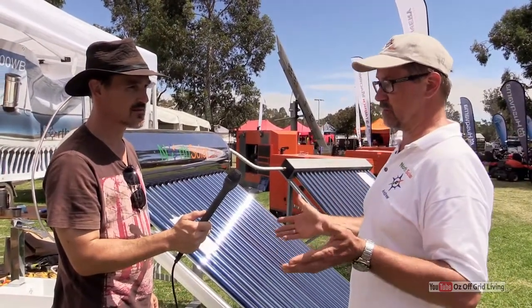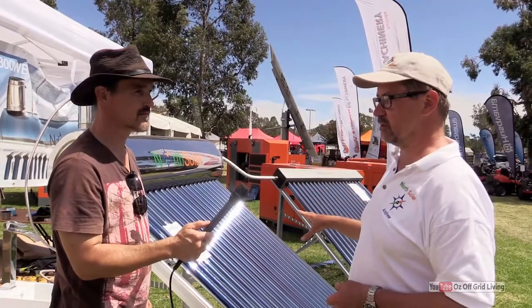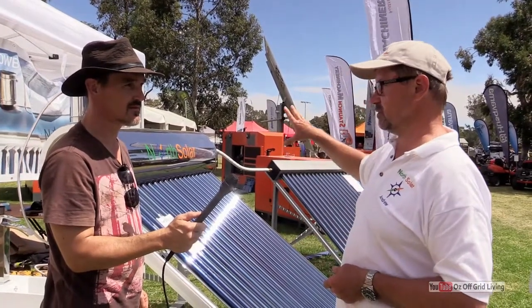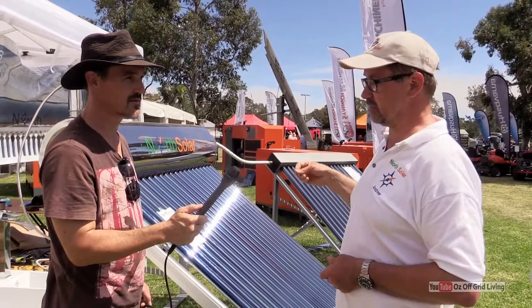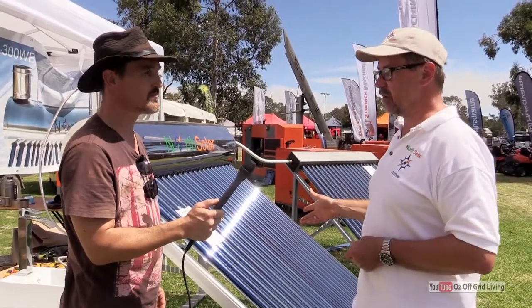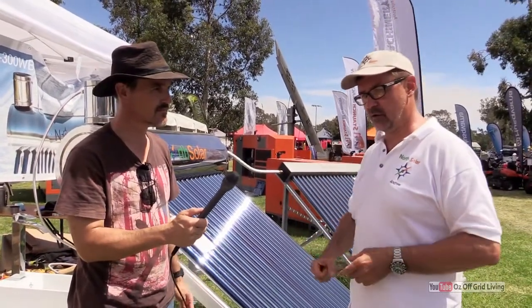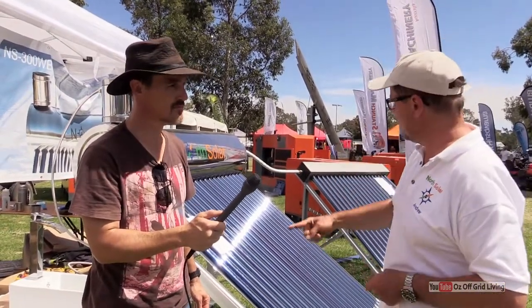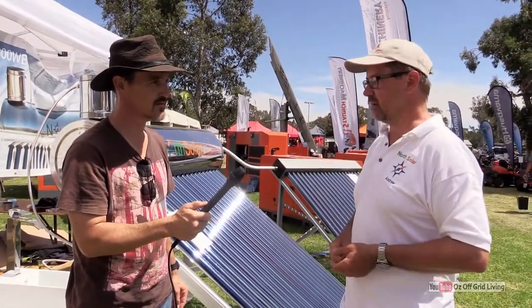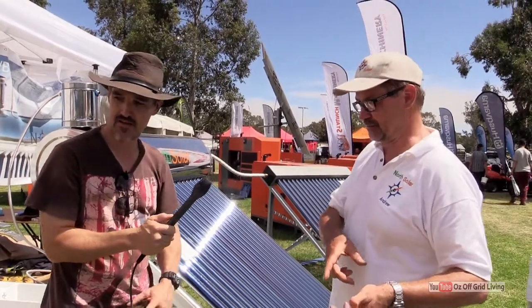If the sun is not out over about a one to two week period — which happens in Melbourne over winter — it still raises the temperature of the water to between 20 and 30 degrees. So in that scenario you may need a booster. In an ideal situation you will have one of these units running into either an instantaneous gas system, or you can modulate them to a wet flue which goes onto a wood heater, or a wetback stove which has water running through it and then goes back into the main tank. If you're using a wet flue or a wetback, you've got an infinite amount of hot water — assuming you actually light your stove.